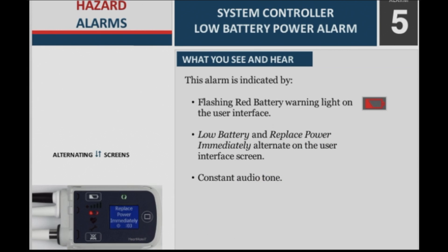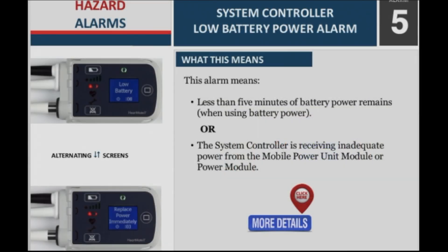System controller low battery power alarm — what you see and hear. This alarm is indicated by: a flashing red battery warning light on the user interface; low battery and replace power immediately alternate on the user interface screen; and a constant audio tone. What this means: Less than 5 minutes of battery power remains when using battery power, or the system controller is receiving inadequate power from the mobile power unit module or power module.